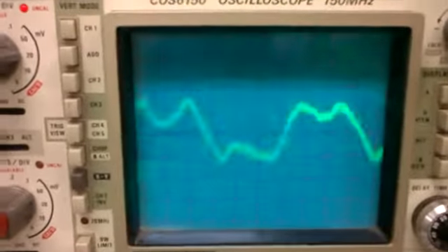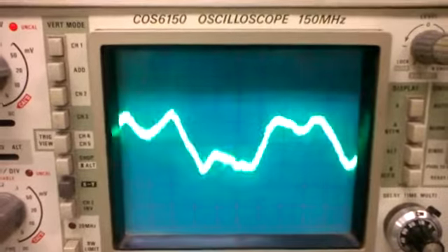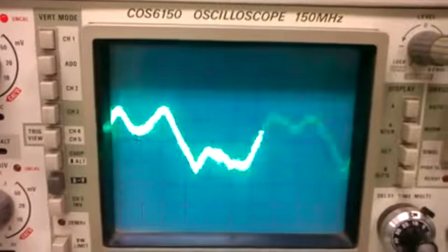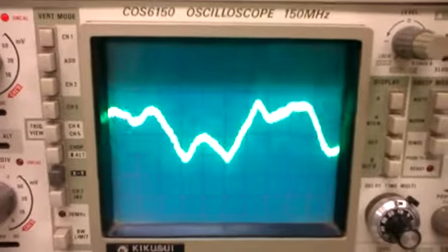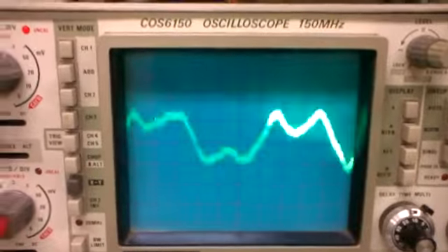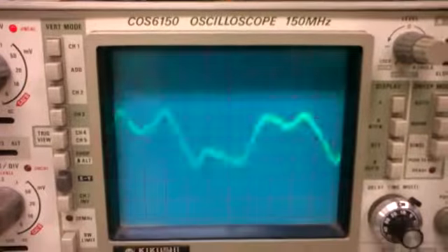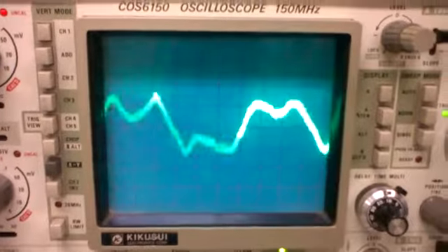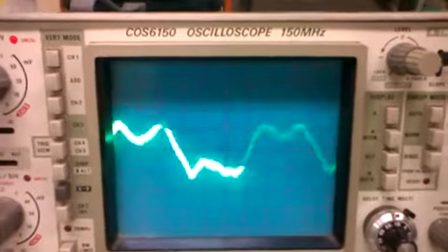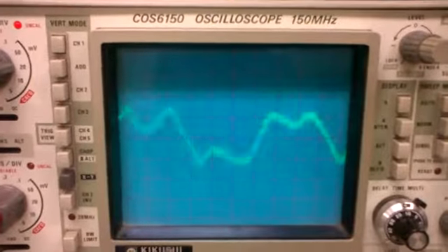Now what we're actually seeing is an AC signature which is coming back through the neutral earth. The MEN link, which is typically connected together in buildings, is putting a little bit of background noise into the machine. And so this is basically pretty much a form of induction into that ring loop, which is being fed back.